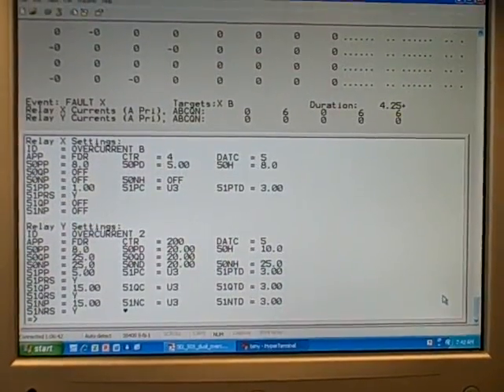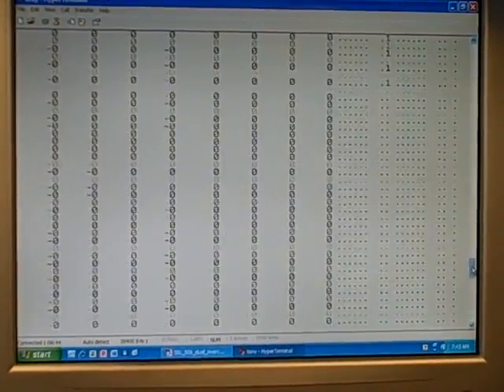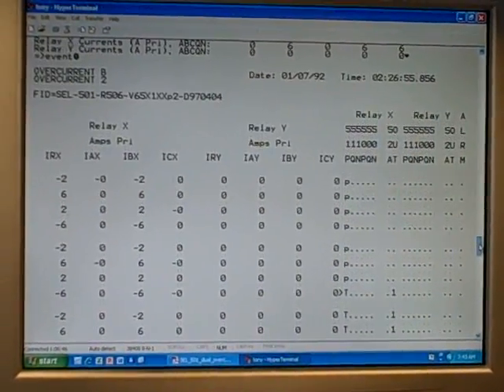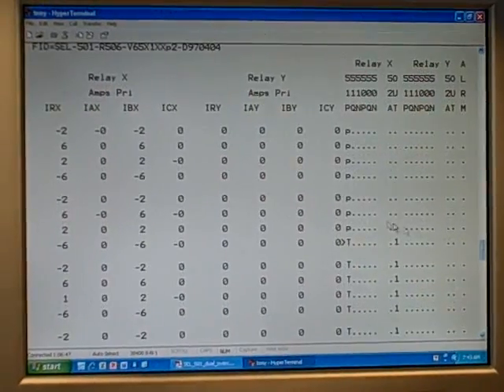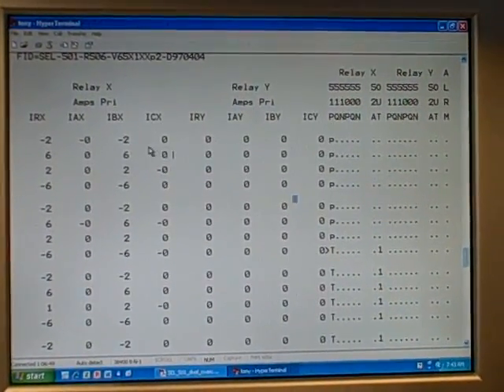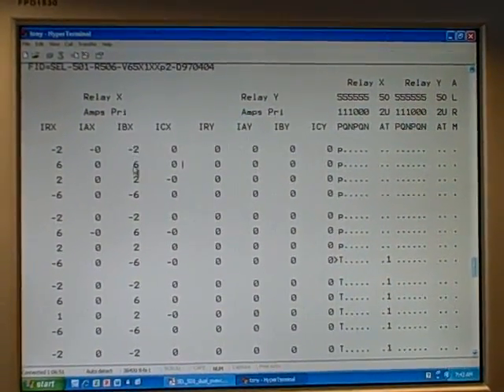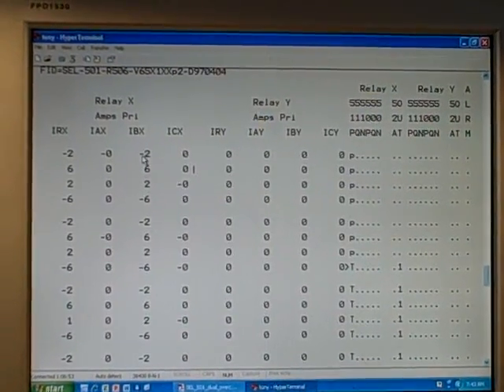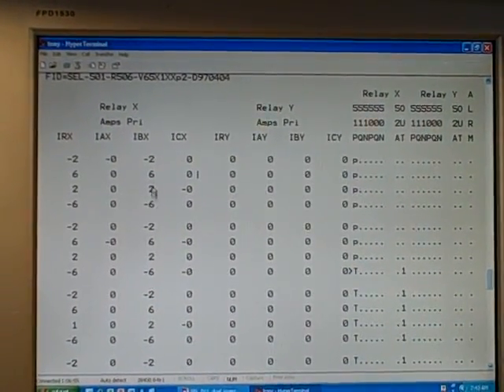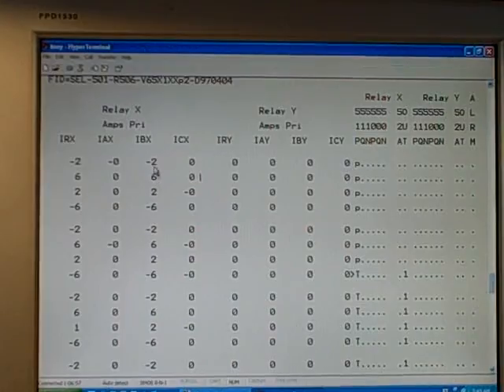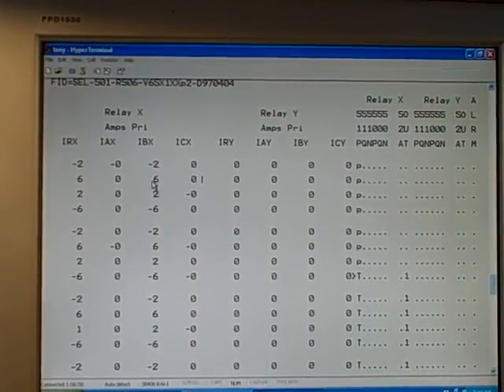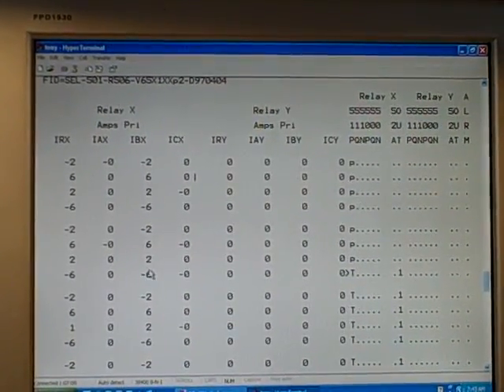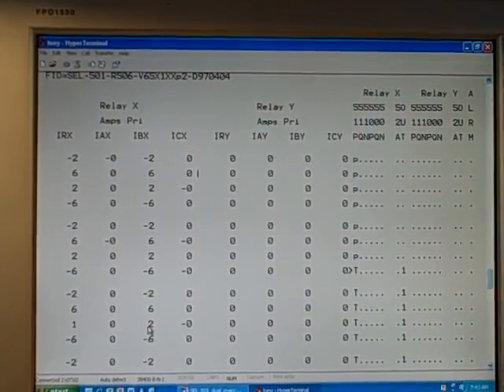It records 15 cycles worth of history. So if I come up here, what I see is relay X is indicating the current. This is instantaneous current values taken at quarter cycle intervals over time. So these four rows constitute one cycle of the AC power, these four rows another cycle, these four rows another cycle.